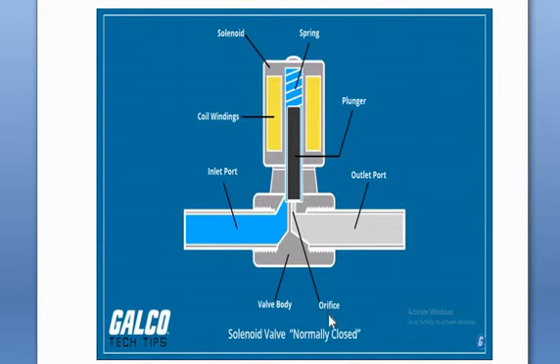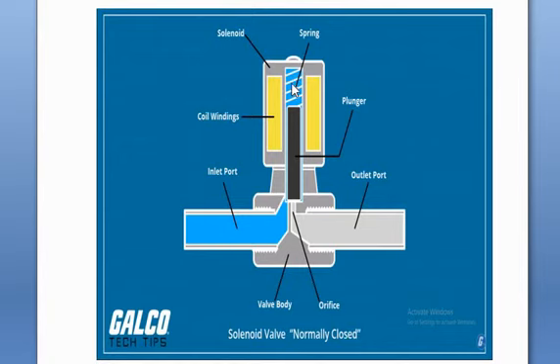This is an inlet of water, but the water is not flowing because the solenoid valve is stuck. The solenoid valve is not opening; when the solenoid valve is open, the material or liquid is sent to the outlet port.